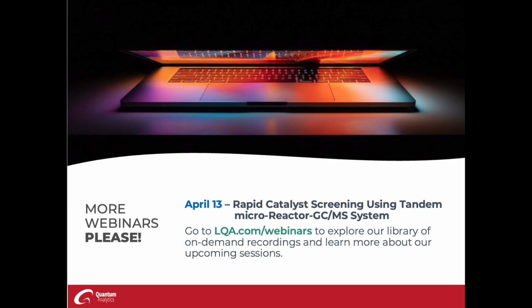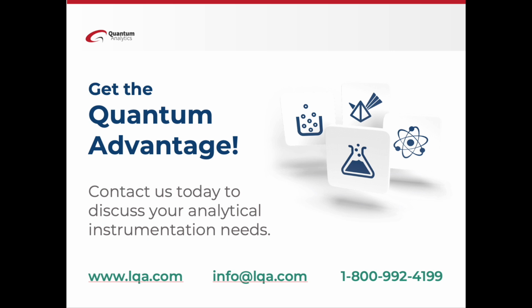So first up, how easy is it to change your RGA orifices and maintain the MS interface? It's actually very simple. I think Terry mentioned several times during his presentation that the orifice plates are simply VCR discs that have a laser drilled hole in them. And so you just close the isolation valve to the mass spectrometer, which protects the mass spectrometer, turn off the bypass pump to remove the vacuum from the interface, and then you just use a couple of wrenches to spin off the VCR fittings and replace the orifice with a new one, a different size, or let's say your orifice has become plugged. And then you just do the reverse process, spin it back on, turn the bypass pump back on, and then open the isolation valve, and you're ready to go again. So it's very simple to make that change if you need to.